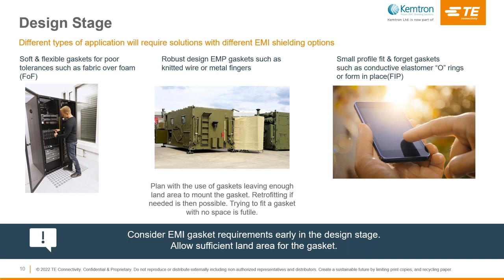EMI gasket mounting should be considered early on in the design stage. Trying to retrofit a gasket on a flange that wasn't designed to take one will narrow your gasket options or be unattainable, and some redesigning may be required. As a general rule, the more land area available to fit the gasket, the greater the options. Different types of applications require different types of EMI gasket — for example, a typical cabinet enclosure will require a soft and flexible gasket such as a conductive fabric-over-foam gasket, a military shelter will require gaskets such as knitted wire or metal fingers, and small devices may need conductive elastomer O-rings or form-in-place gaskets.